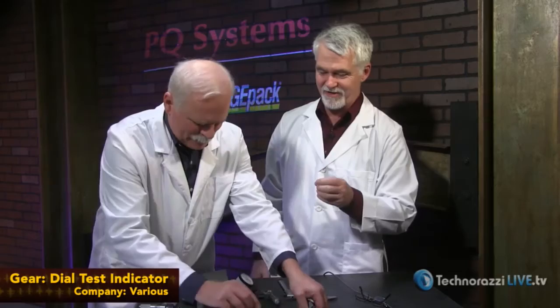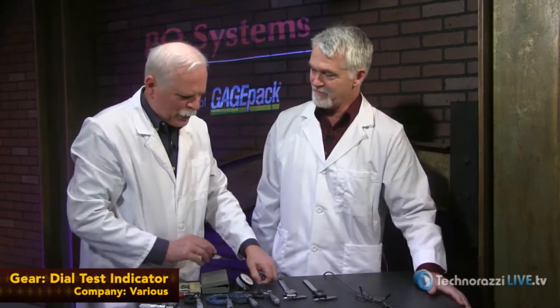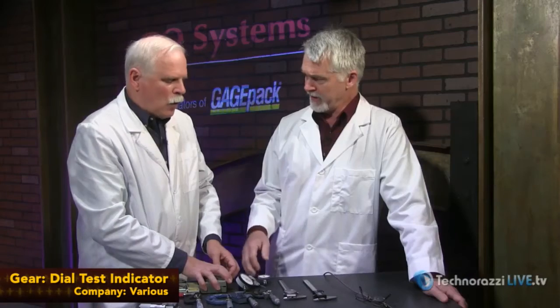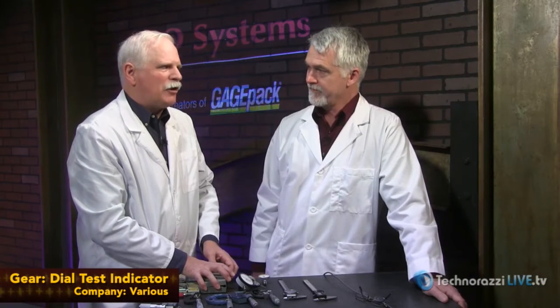So if somebody has an indicator for sale, and they say, look, it has all these different tips with it, and you've got a 1/4 inch tip and a 1/2 inch tip and a 2 inch tip, you might be suspicious. That's a clue. They might not know what tip goes on there correctly, and that's not something you could field check unless you happen to bring standards. Or if you knew the model, you could look up the model number, which would tell you what tip. Most of the Brown & Sharpes are going to be a 1/2 inch, although every manufacturer seems to make one with the long one, so you would have to know the models.